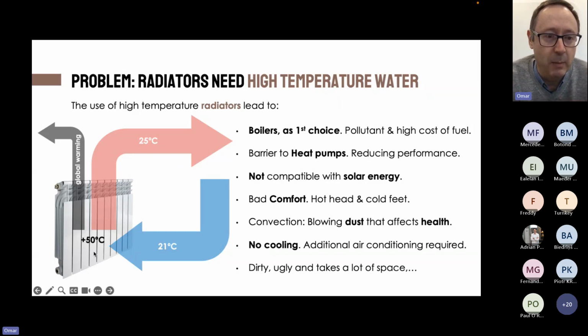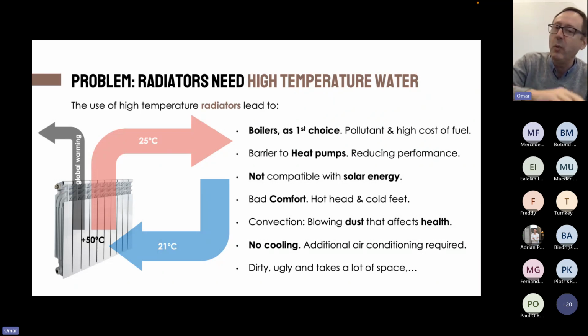As well, these so-called radiators, we call them natural convectors without fan. They are not compatible with solar energy. They provide bad comfort because, as we said, they heat up the air, and then you have this situation where your head is hot and your feet are cold, which is not good comfort. And because we have this movement of air, we are blowing the dust, which is something that affects health. When you remove radiators and truly implement radiating plates and get rid of convection, the dust disappears. You remove the energy in the air, the dust goes to the floor, and the vacuum cleaner removes it all. It's something that we have learned together with our customers with the transformation of old buildings throughout these last couple of years.